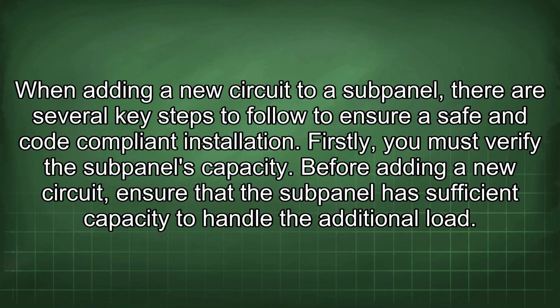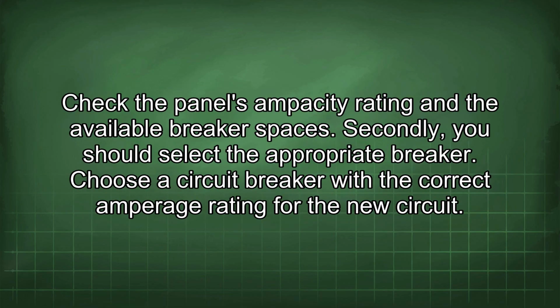Firstly, you must verify the subpanel's capacity. Before adding a new circuit, ensure that the subpanel has sufficient capacity to handle the additional load. Check the panel's ampacity rating and the available breaker spaces.